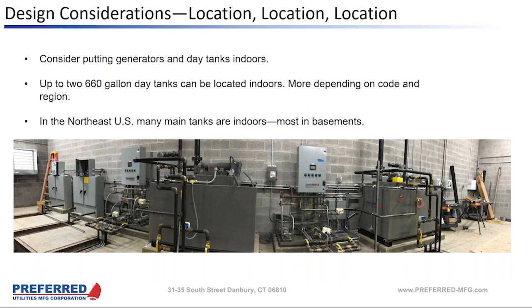I'd also point out in this picture right here, you see off to the left there, we have some polishing units. It's important to remember that while we try to mitigate water in different areas of the system, obviously it's bad for the fuel, it gets worse with cold weather, keeping in mind that there are a few spots where we're intending water to accumulate, and that includes the reservoir in a polishing unit. So if that polishing unit is designed to pull water out of fuel, you want to take into consideration that there may be water in that reservoir in there. So that may dictate either adding a heater to that enclosure or having that in a space that's going to stay warm.